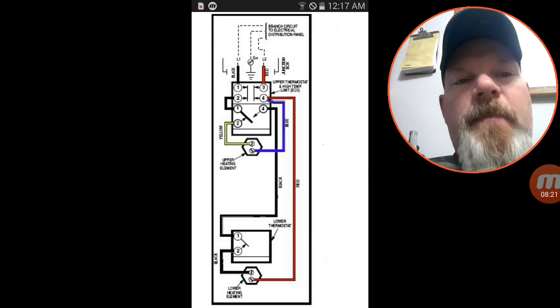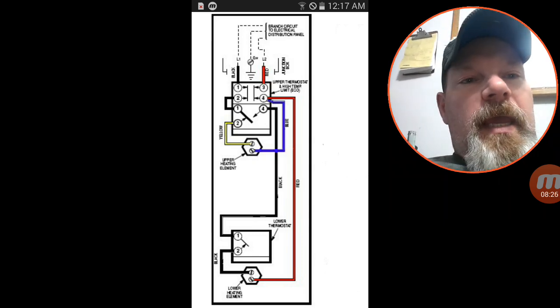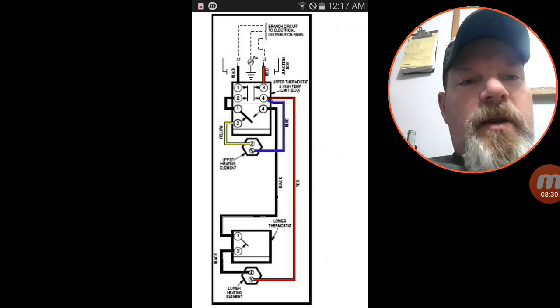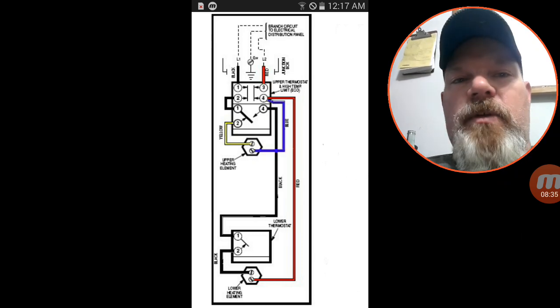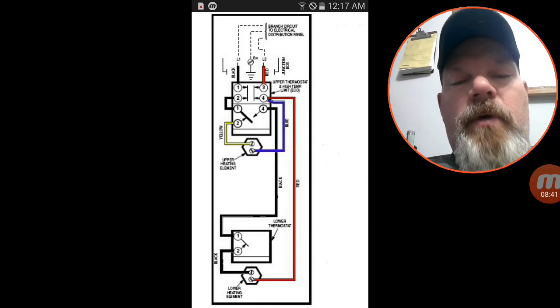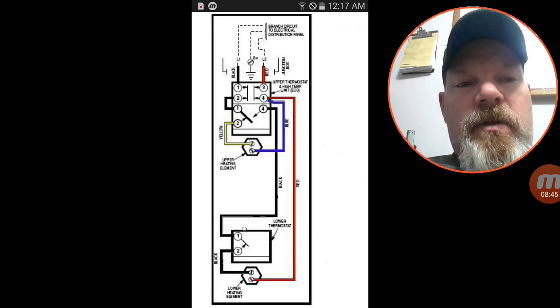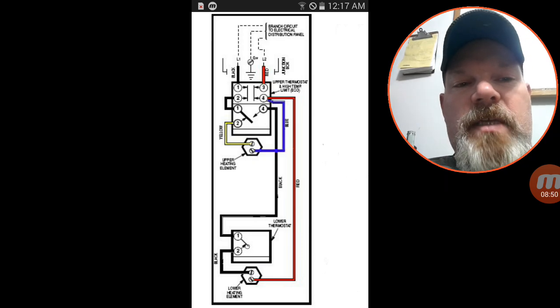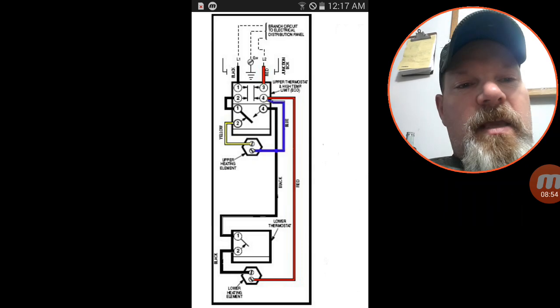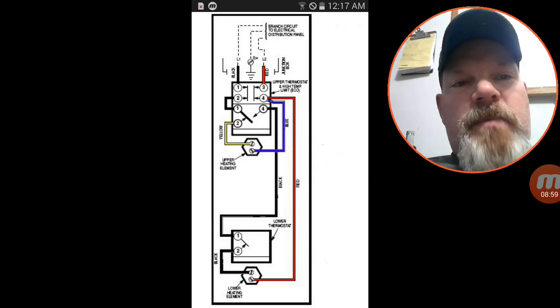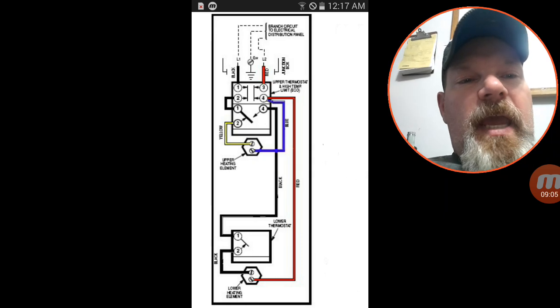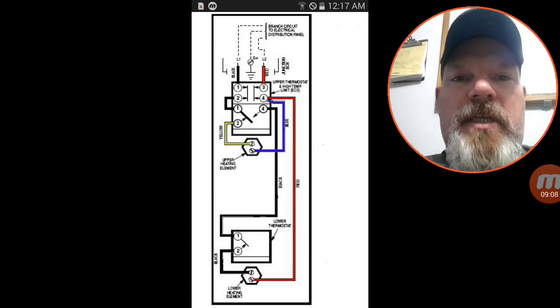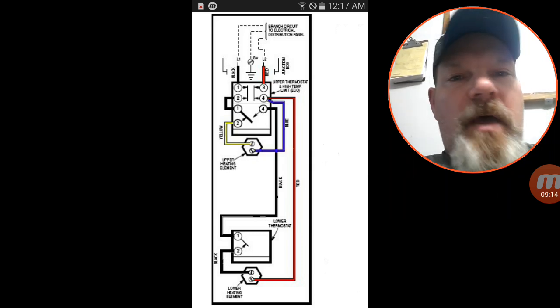All right, so now what happens is you stop using water. The top element is calling, or the top thermostat is calling and powering up that upper element, and it will continue in that state until the upper portion of the tank is satisfied and that thermostat says, hey, we're good on temperature, and it satisfies and switches back to number four, sends power down to that lower element. This lower element then, because it's still cold, this thermostat's calling and is sending power down to this one. So once this thermostat senses that the lower portion of the tank is satisfied, this thermostat will open and everything will just be then sitting waiting for the next call for heat. Okay, that is basically an electric water heater in a nutshell. That is the entire wiring schematic, that is the entire operation. There's really nothing more to it.